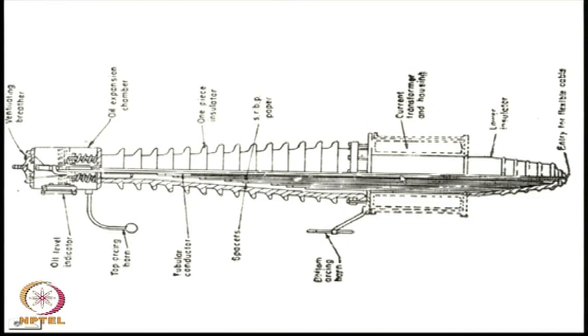There is another type of bushing construction which is called the capacitor type, in which alternate layers of metallic conductor and insulating material are wound in a cylindrical fashion to form a series of capacitors between the inside conductor, the high voltage conductor, and the outside plane, which is normally earth. So, the radial potential distribution along the radial direction of the bushing is equally divided.